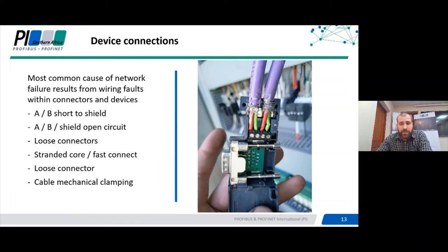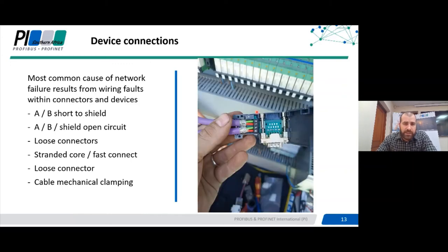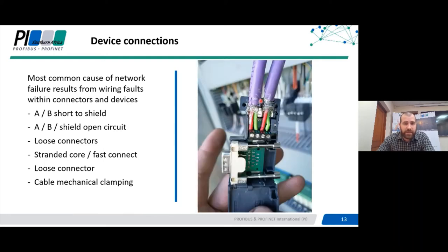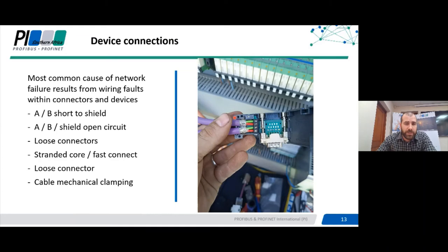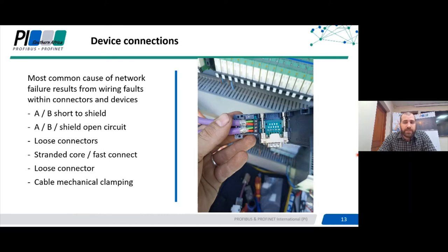Sometimes connectors aren't screwed properly into devices, especially devices that vibrate such as VSDs and panels of large mobile machinery — this can result in intermittent comms loss, so ensure those screws are tightly fastened. This is an example of a well terminated plug using a proper stripping tool — the shields of both cables are making good contact with the ground bar, and the cables are in a position providing good mechanical strength clamped by the teeth within the plug. Within Profibus cable you get two types: solid core and stranded core. Stranded core cables should only really be used where the cable is required to bend continuously, such as in energy chains.